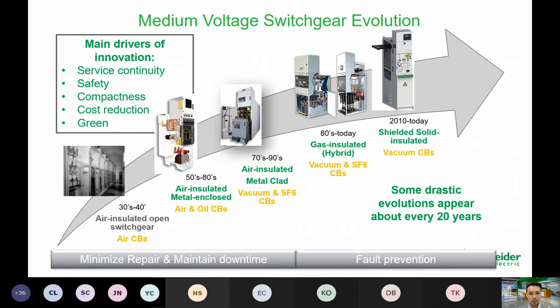For gas insulated switchgear, generally they are using a lot of the vacuum and SF6 options. All right, one of the key factors is that air insulated switchgear has one good feature as well, the withdrawable circuit breaker, where you can draw out the circuit breaker to a place for maintenance. But this drawing out also introduces certain issues, because for a drawout feature there is more mechanism in place. For example, there will be connector issues where they develop weak links.